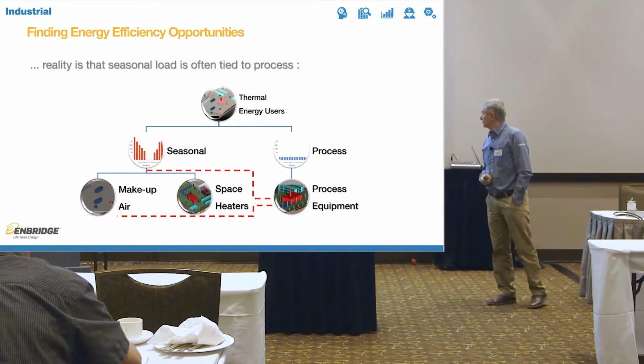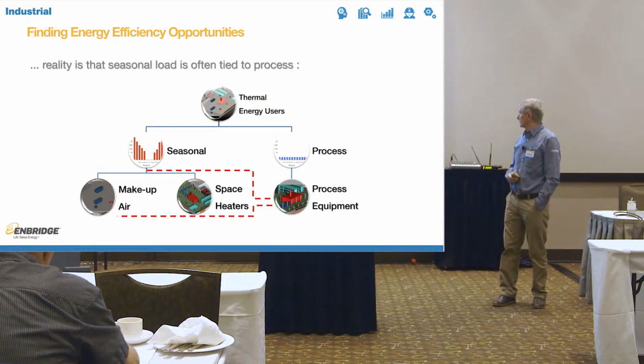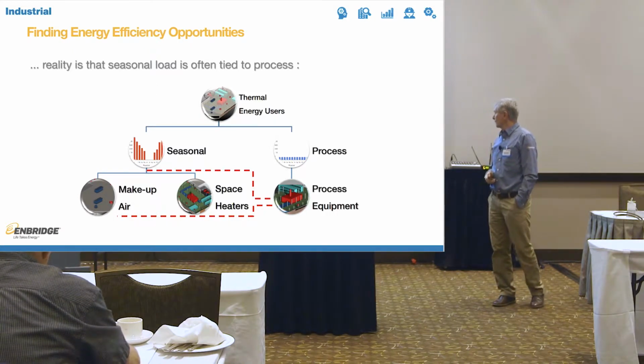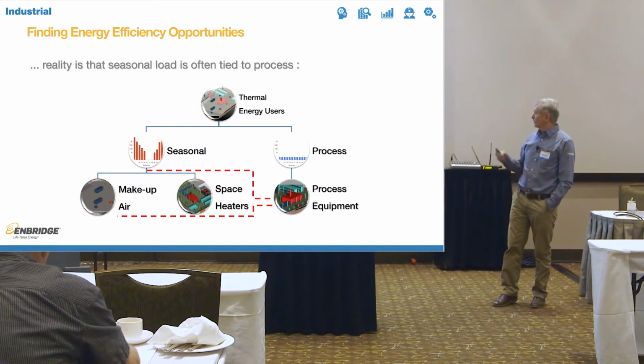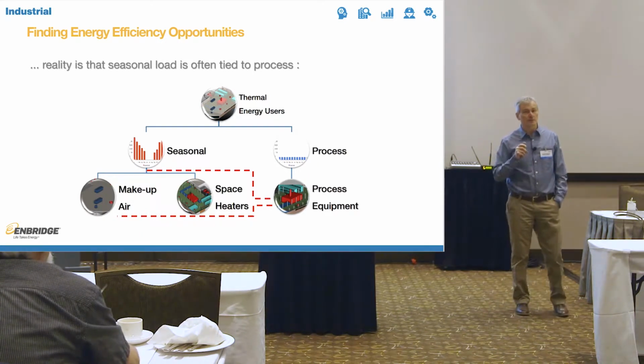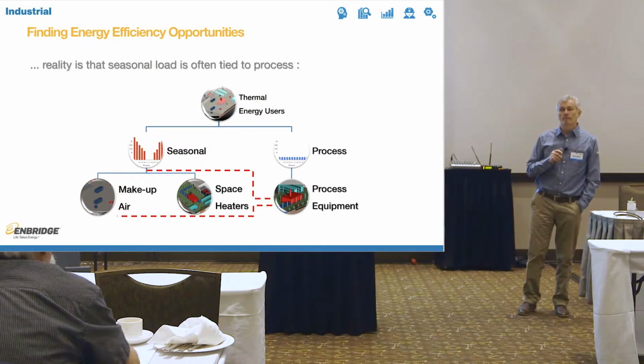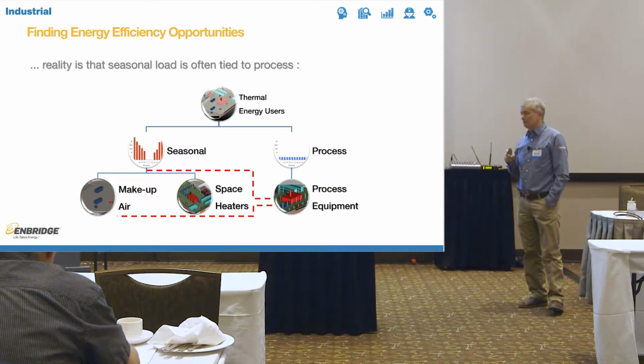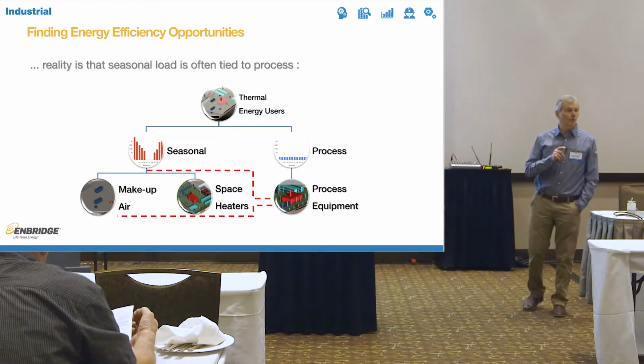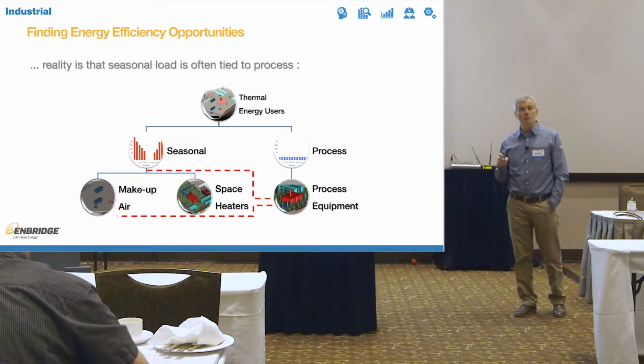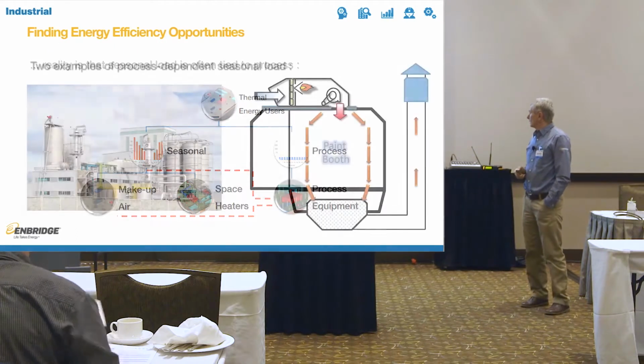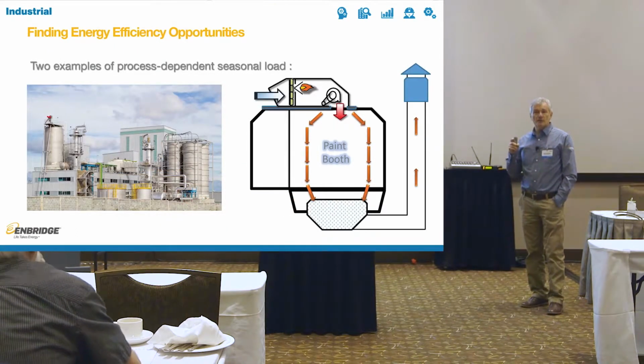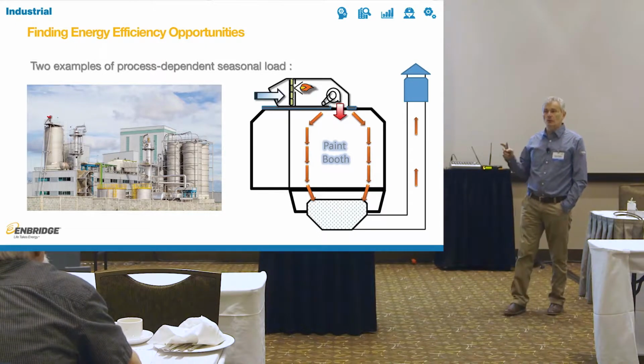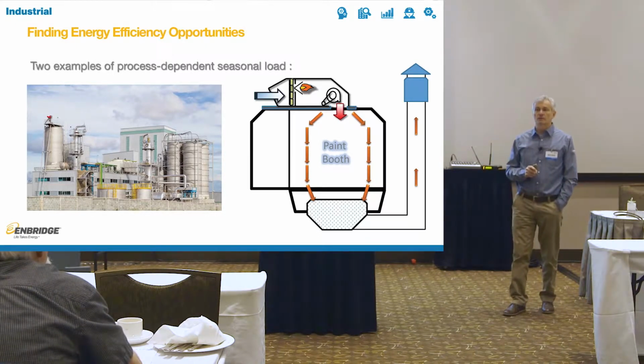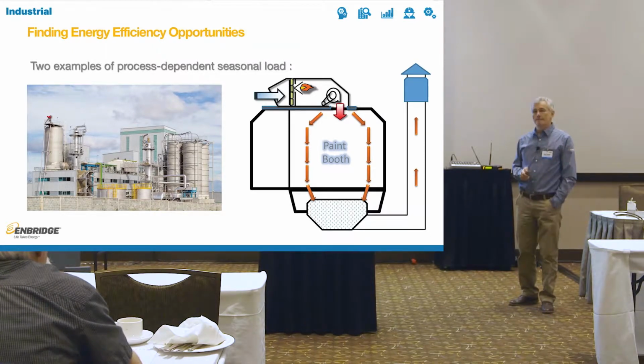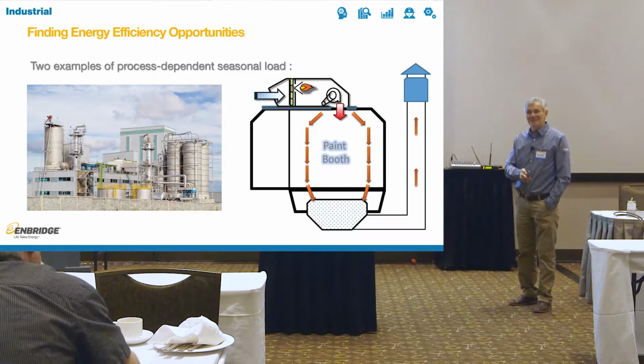But when you really look at it, and you split that and look at it this way, how many of you will actually find that your makeup air is influenced by your process load, really? So therefore, your makeup air plays a far more important role for most of you than just space heating, or hopefully it does. And therefore, can anybody think of two examples of the seasonal load that's dependent on the process? Bill? Paint.